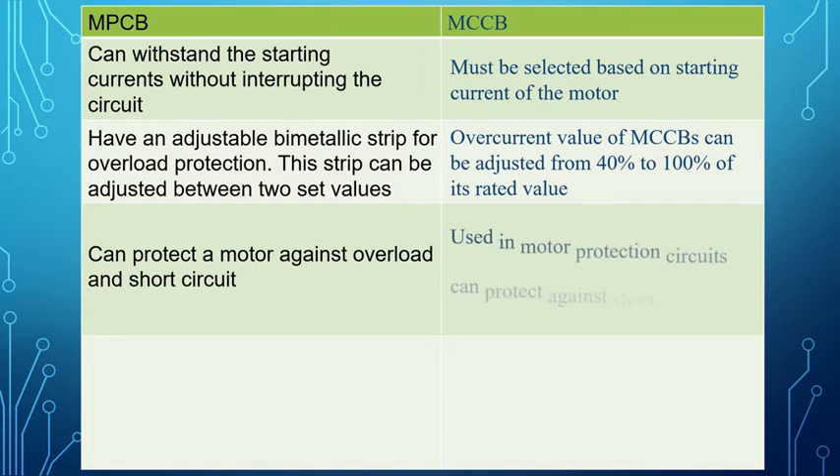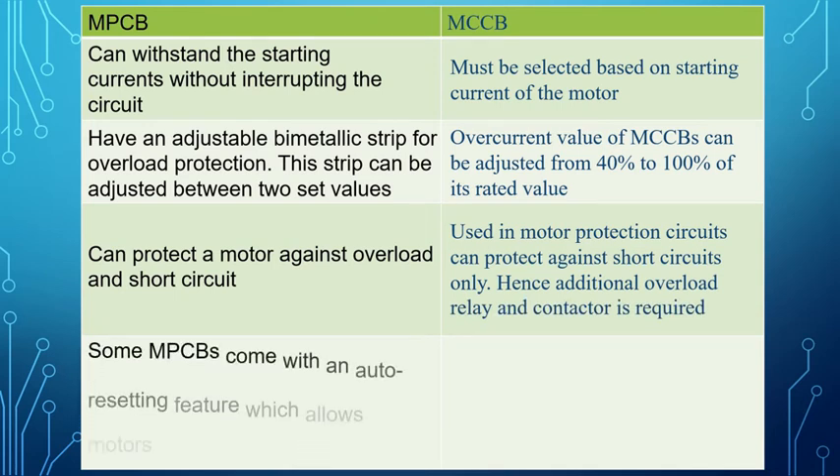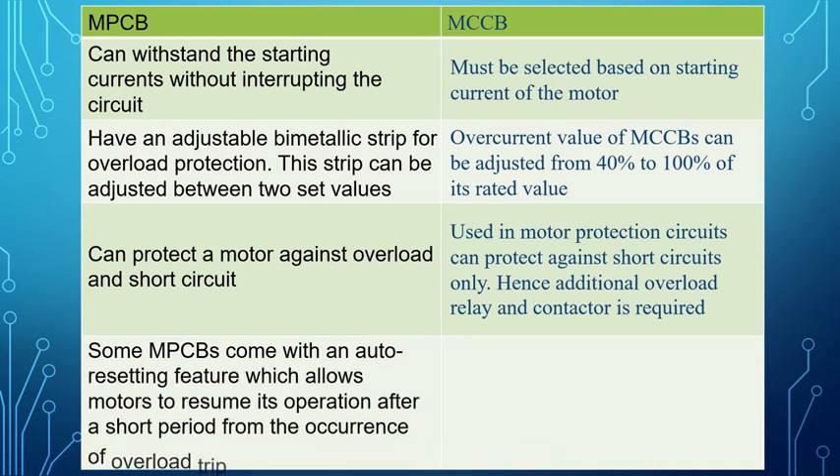MCCB is used in motor protection circuits, can protect against short circuits only — hence an additional overload relay and contactor is required. Some MPCBs come with an auto resetting feature which allows motors to resume operation after a short period from the occurrence of an overload trip.